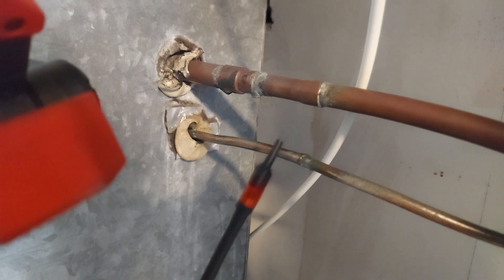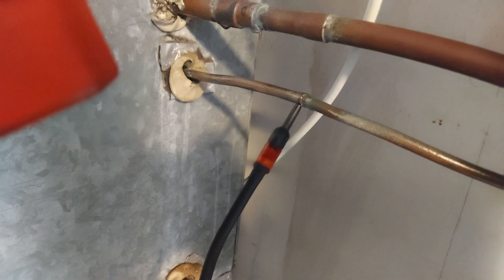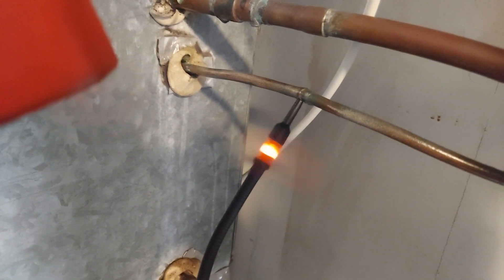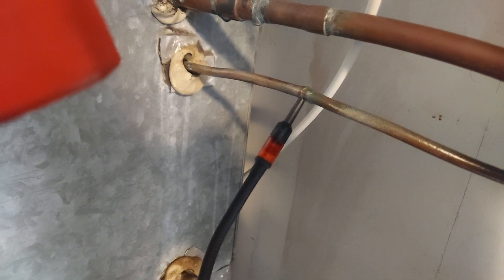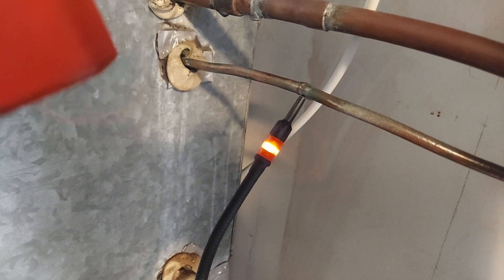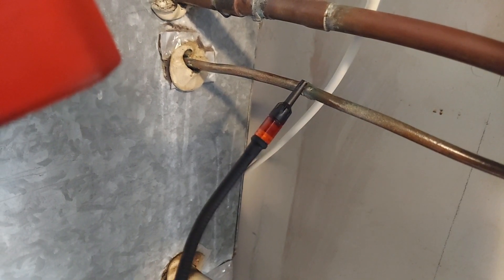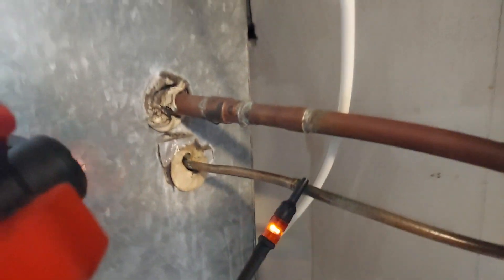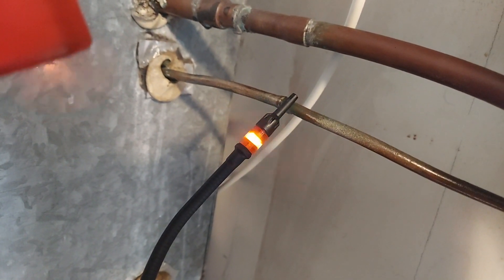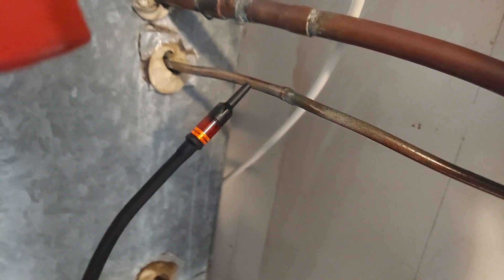I'm touching the top pipe but if I go down here I can leave it there - it will never stop. The leak is confirmed on here; I can see the oil and everything. Potentially up top could have a leak too, but I rather doubt it. This is where it's at - it is staying on for a long time.